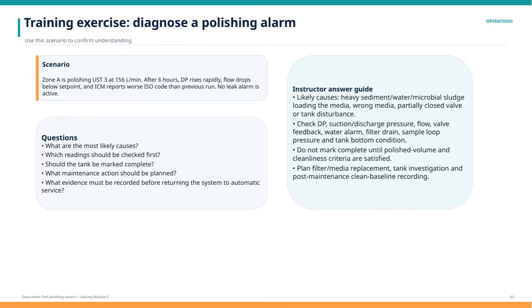For maintenance, you should plan to replace the filter media, conduct a thorough tank investigation, and take post-maintenance baseline cleanliness recordings to ensure everything is back to optimal condition before returning the system to automatic service. This approach will help diagnose and resolve polishing alarms effectively, maintaining fuel quality and system reliability.